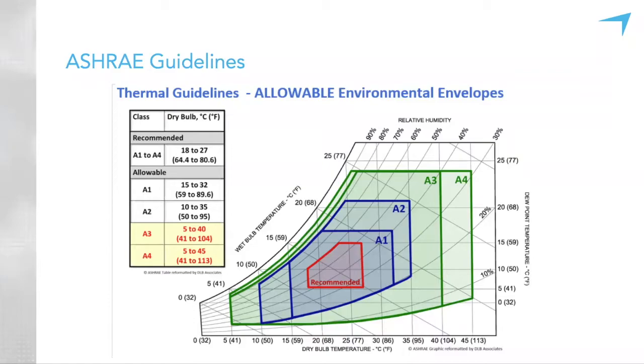As we expand into class A2, A3, and A4 servers, you can see the huge temperature ranges they show us here. So the recommended range was very small, but then there's an allowable range that tells us the server, switch, and storage manufacturers are making their equipment more dense, doing everything in their design capabilities to make servers more efficient without such a deep need for extra cooling.